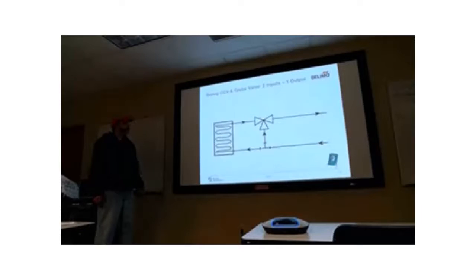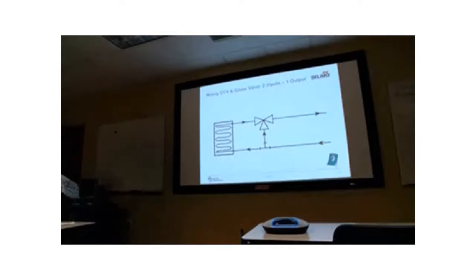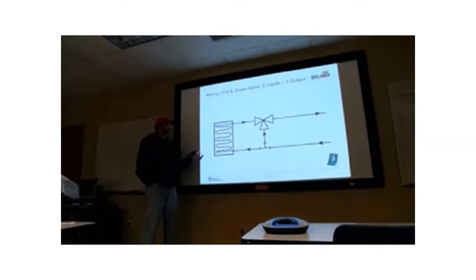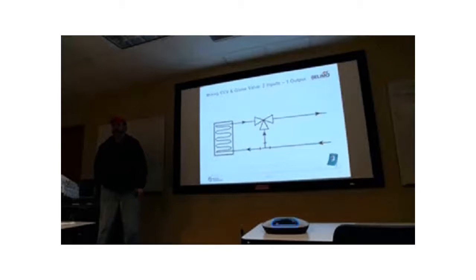Went through that. So now what we're going to do, if you guys want to follow along, see where I'm at here. I guess I'm on page 34 if you're in the workbook. So here is what we call mixing service for a three-way valve. And all's right with the world here, right? Because we know most of those valves are on the return side, right? In almost every coil that most of the coils you guys go through. Have you guys ever seen three-way valves on the supply side? For a coil? It's not real common around here, but it does the same thing. It'd be a mixing. It'd be a diverting.